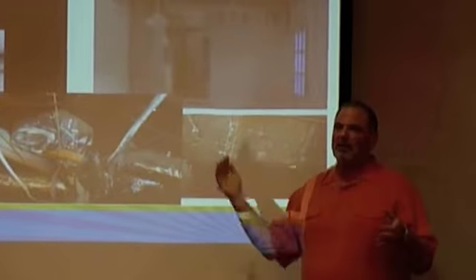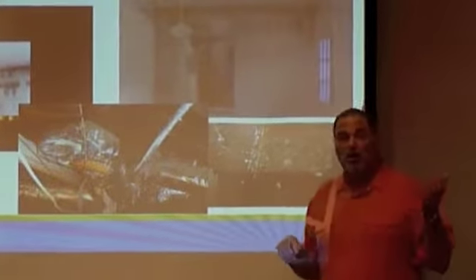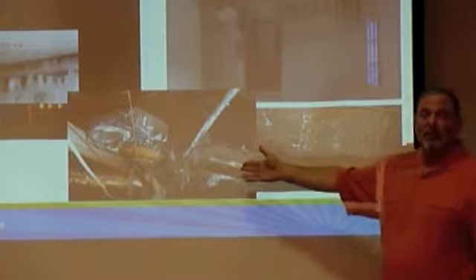We really don't like to see it strung over everything like this because you're just killing your equipment. You're shortening the life of your equipment, you make it work harder, and it's costing you a lot of money because you're not getting the airflow that you need in the home. So this is something I see often. New construction, old construction, we see it all over the board.